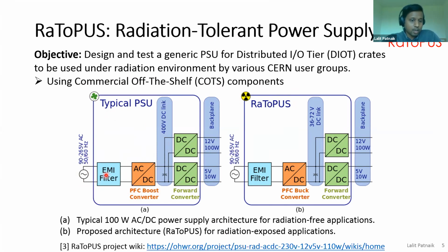After the EMI filtering, you have an AC-DC stage, then some kind of high, or 400-volt, DC link generated by this AC-DC stage, followed by any number of DC-DC stages to generate the required backplane voltages required by the system. This typically uses what is called a power factor correction boost converter.